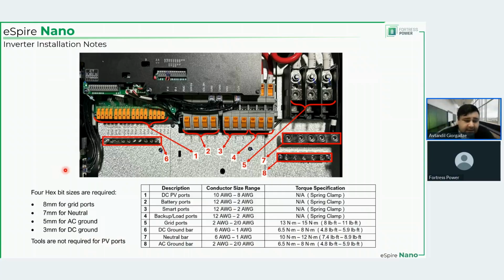Then cables that connect to the inverter. So DC PV ports, 10 gauge to 8 gauge, battery ports, 12 gauge to 2 gauge, smart ports, the same thing, same for the backup ports, grid ports, 2 AWG to 2/0 AWG. DC ground bus bar 6 to 1, same for the neutral, and AC ground 2 to 2/0 AWG. Now, torque specifications are not given for anything but grid ports, DC ground bar, neutral bar, and AC ground bar, because these are spring clamps, right?